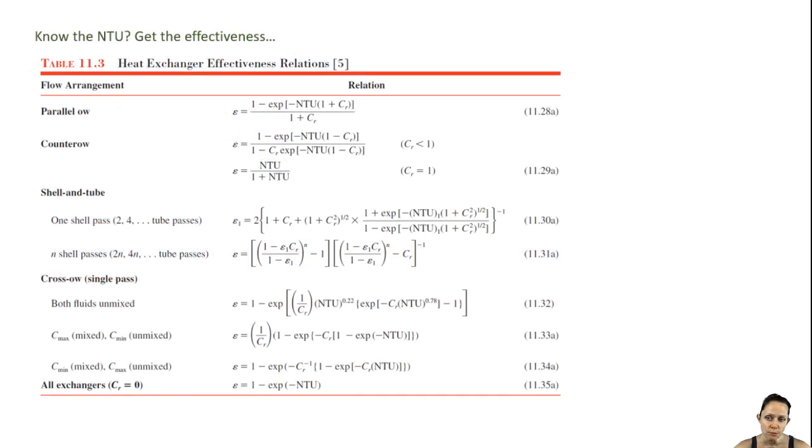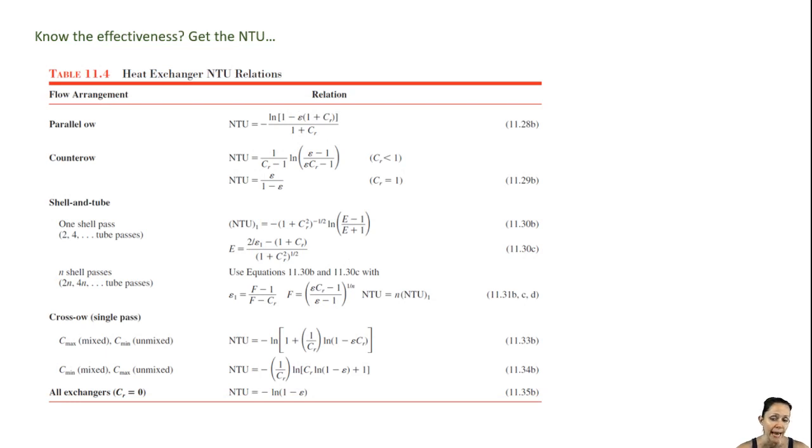Table 11.3 in your book allows you to, for a given heat exchanger type—parallel flow, counter flow, etc.—calculate the Effectiveness based on the number of transfer units and the specific heat ratio. Table 11.4 allows you to work backwards and calculate the NTU based on the Effectiveness and the specific heat ratio.